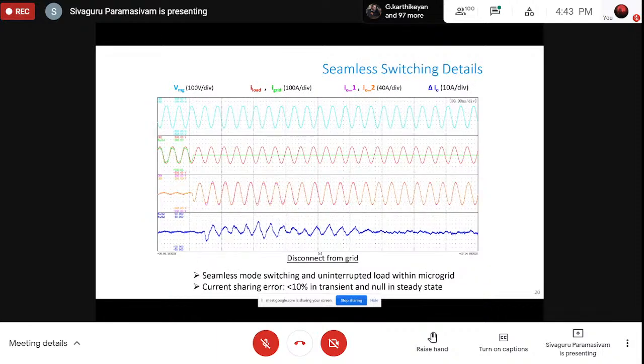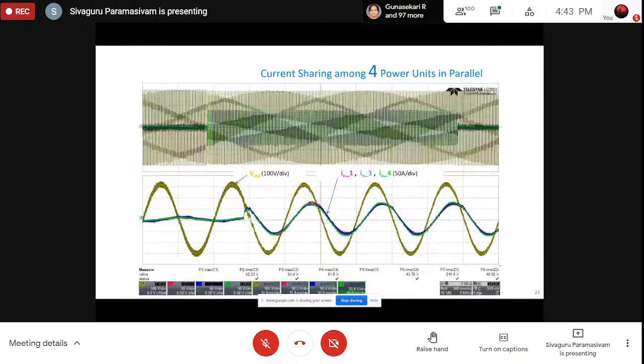This is a similar graph of both voltage and current. This particular graph is for when we have 4 inverters in parallel, because we need more power. When we need 400 megawatts of power, but we have only 100 megawatts, or even kilowatts, of inverters, we need to parallel them, and we need to take care that all of them are working in a synchronized way, and all of them are delivering the power in the same profile and same sinusoidal waveforms.